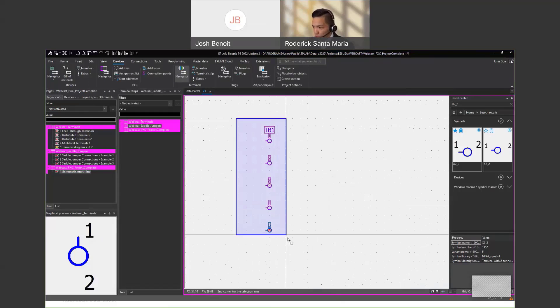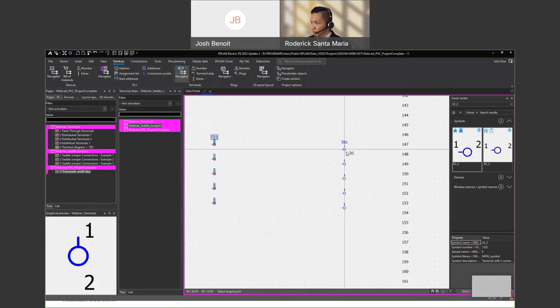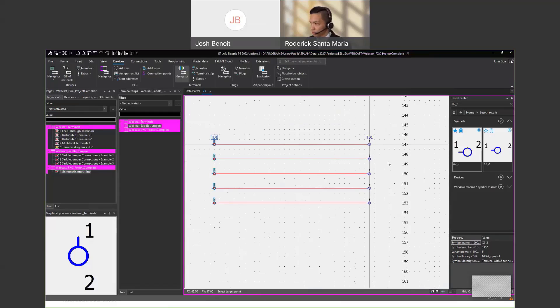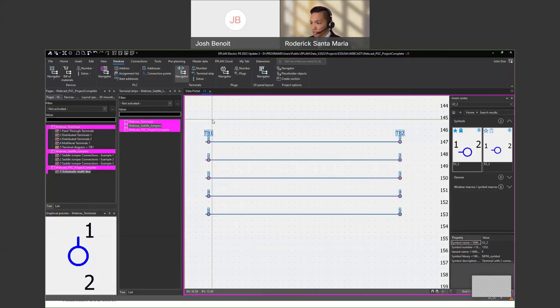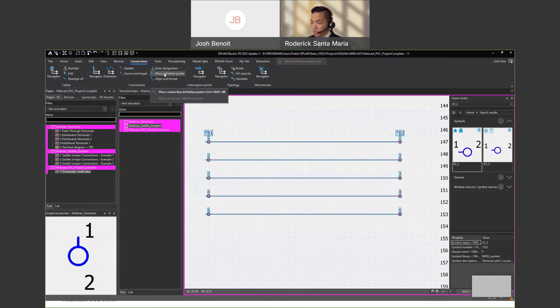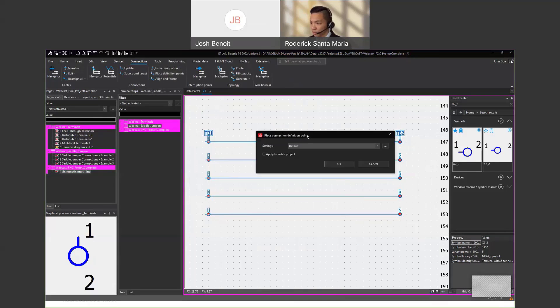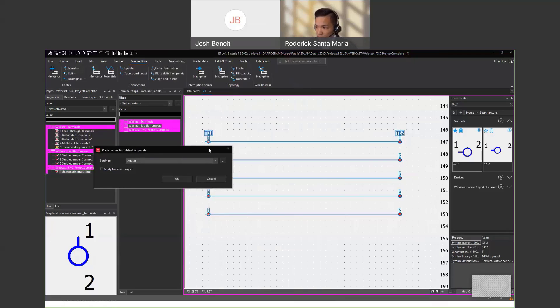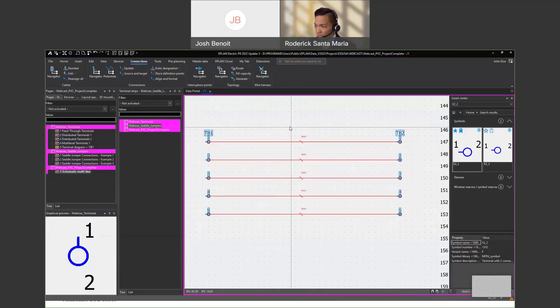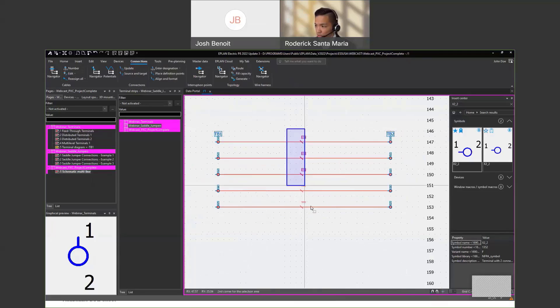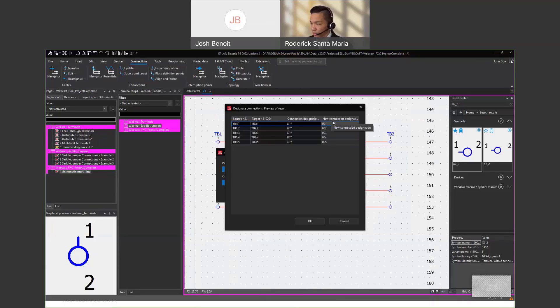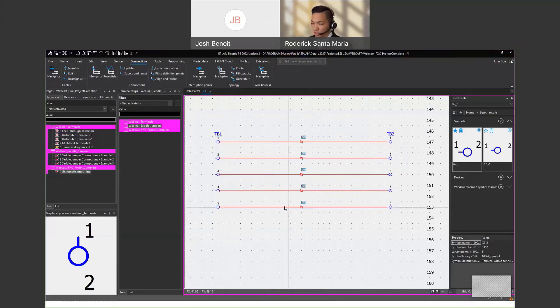I've established my first terminal strip. I'm just going to go ahead and duplicate this so that I have another one next to it and they're connected. Then from here within EPLAN you can actually number your wires using the option to place connection definition points. It'll ask you for a specific scheme — I'll just choose the default — and it'll add these connection definition points, and from here I can set the actual wire designations: 001, 002, all the way to 005 — just sequential.